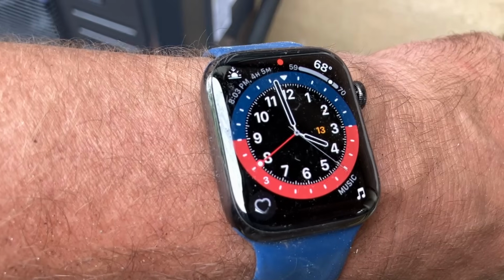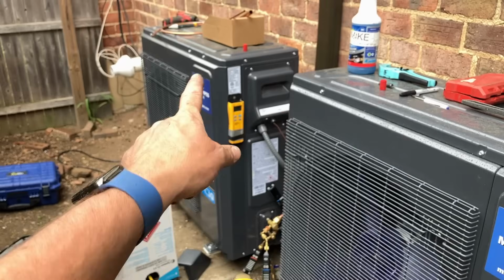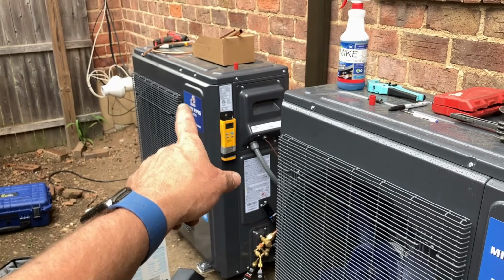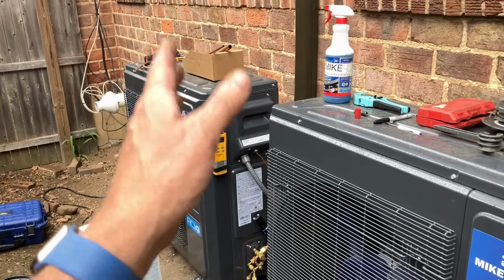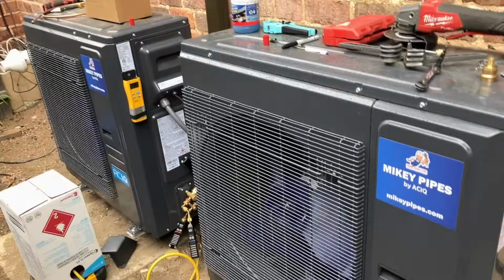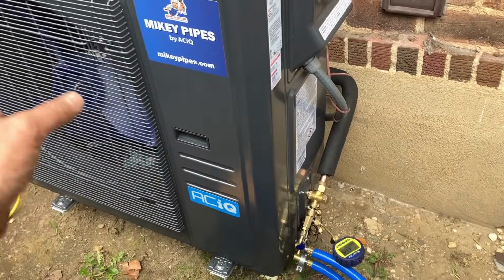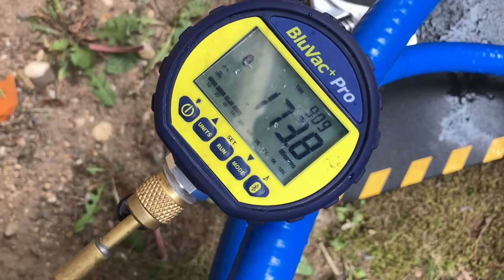A few minutes to 4 in the afternoon. This system's been running for about 45 minutes. I'm waiting for condensation to start flowing into the condensate trap. I'm working on the first floor system. Daniel's wiring it inside. We're at 173 microns.